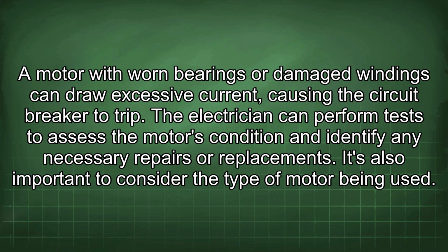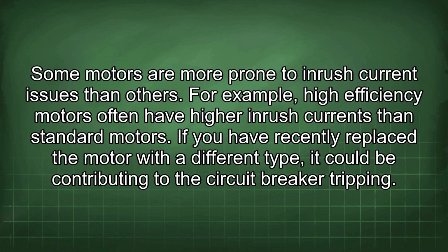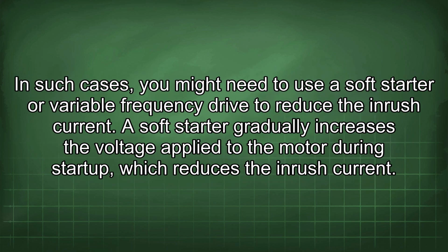It's also important to consider the type of motor being used. Some motors are more prone to inrush current issues than others. For example, high-efficiency motors often have higher inrush currents than standard motors. If you have recently replaced the motor with a different type, it could be contributing to the circuit breaker tripping. In such cases, you might need to use a soft starter or variable frequency drive to reduce the inrush current.